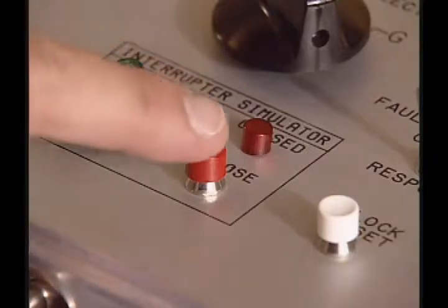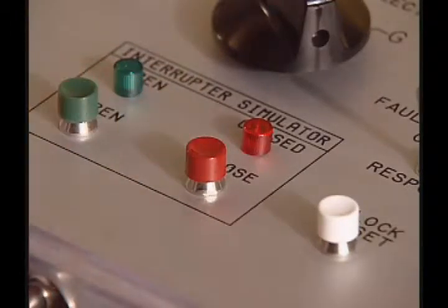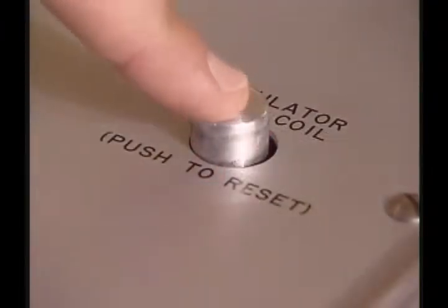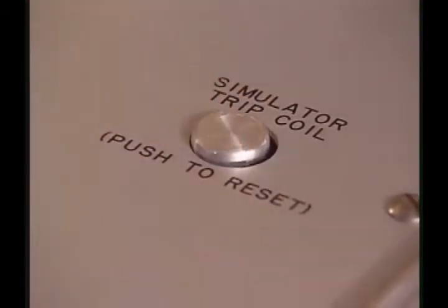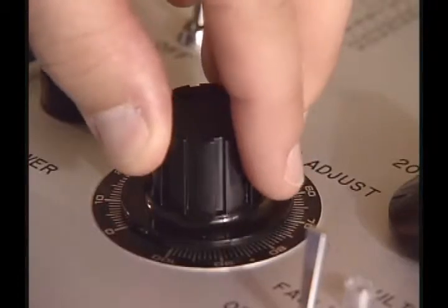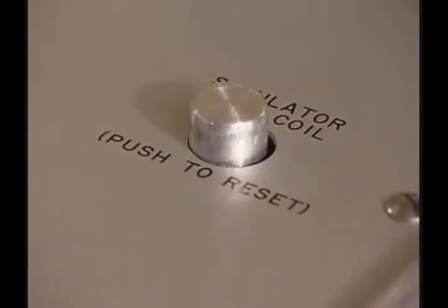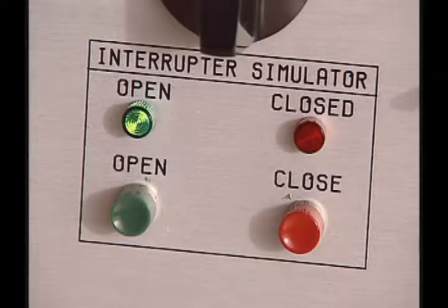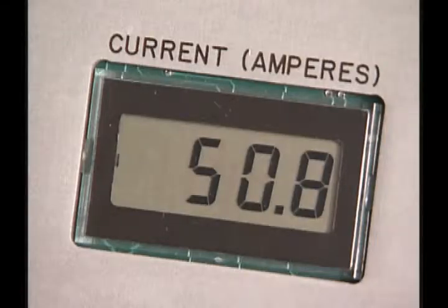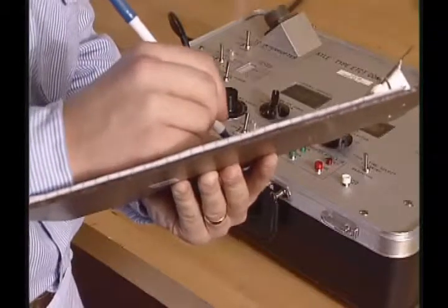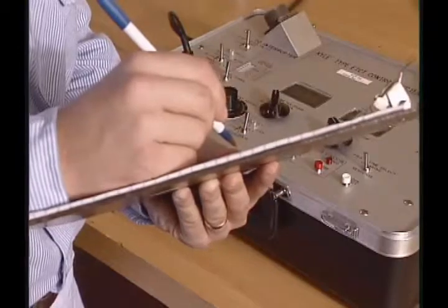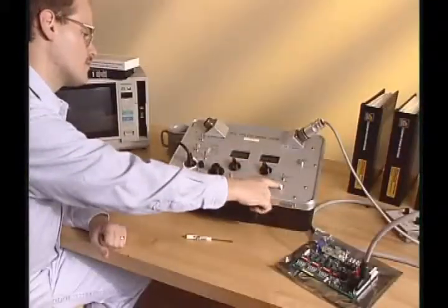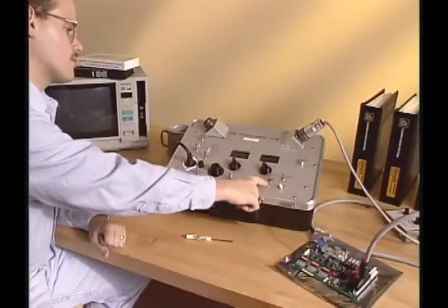Before you begin testing, press the clock reset button. Then press the close button in the panel labeled Interrupter Simulator. Now, to simulate the load, push in the Simulator Trip Coil button to set for tripping. Slowly turn the current adjust knob until the interrupter simulator trips. The green open light will come on. Note and record the current reading on the ETC ammeter display just prior to tripping. Repeat the procedure to test phases B and C.